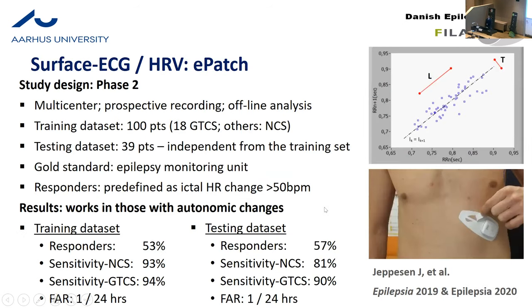We used the square of the L component — what is specific for the seizure — creating a modified cardiac sympathetic index. This red bar marks the seizure, and you can see the increase is really pronounced at the start of the seizure, while during exercise the modified cardiac sympathetic index doesn't come close. We validated this in phase two studies. It works only on patients who have a marked change in heart rate — marked autonomic changes during a seizure — which is however more than half of the population. Within these responders, sensitivity is 81% for non-convulsive seizures and 90% for generalized tonic-clonic seizures, with a false alarm rate of one per day.